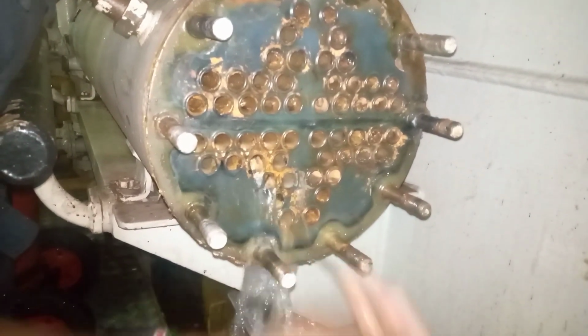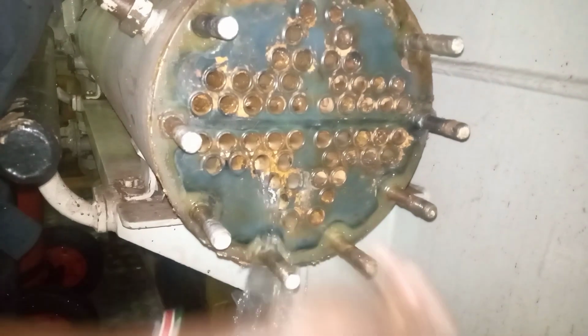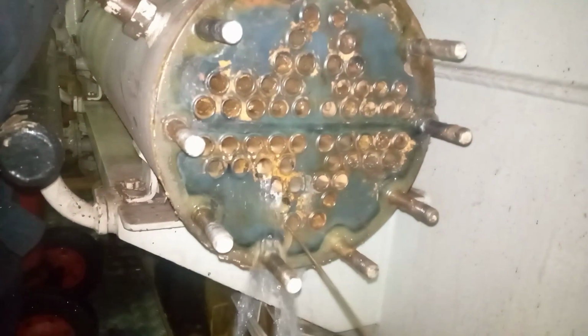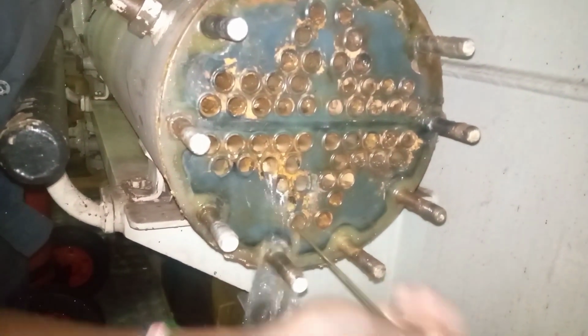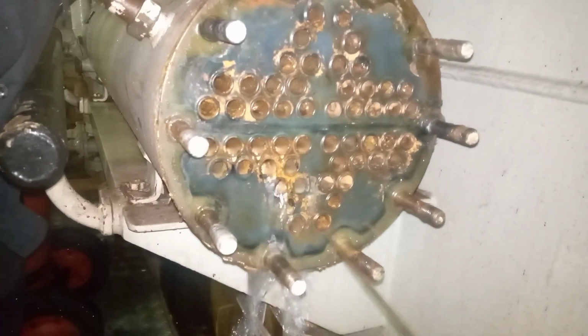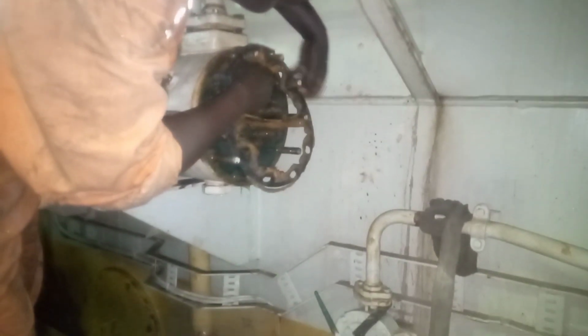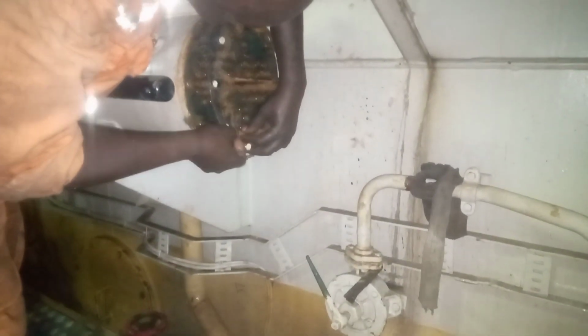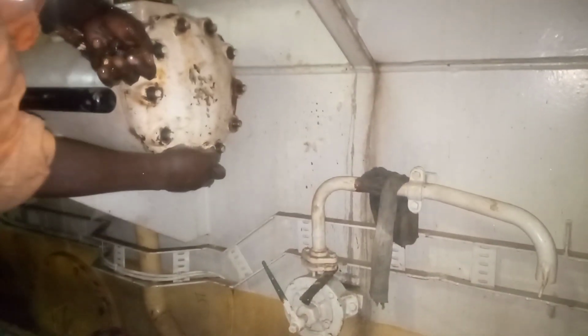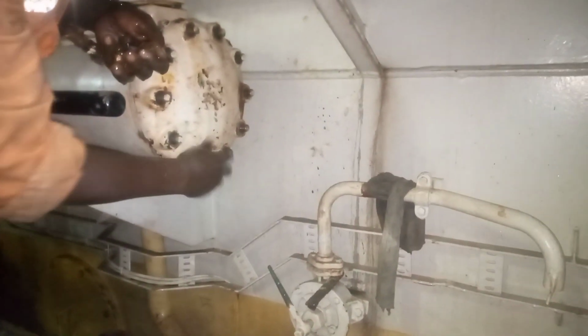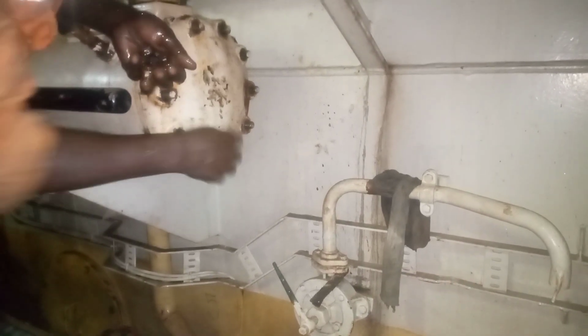This heat exchanger was now clean as compared to when we first opened it, and so it was ready to be used, and therefore we started closing. And to close this end, we just had to reverse the process by first inserting the rubber gasket and then followed by the heat exchanger lid, and then we screwed back the nuts.